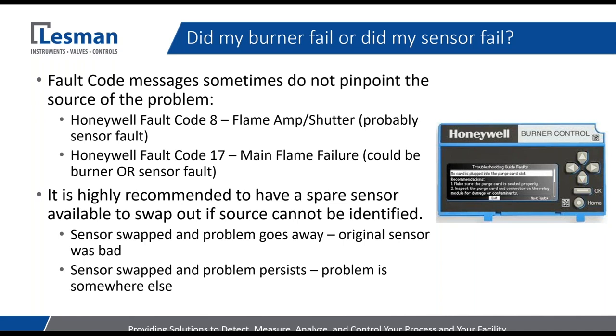We always recommend having some kind of a spare sensor available to swap out. Common troubleshooting practice is to try to identify where the issue could be coming from and change one variable at a time. If you change out the sensor — whether a flame rod or UV sensor — and the problem goes away, it's pretty safe to say the original sensor was the culprit. But if you swap out the sensor and keep having the same problem, then we've got to look elsewhere.